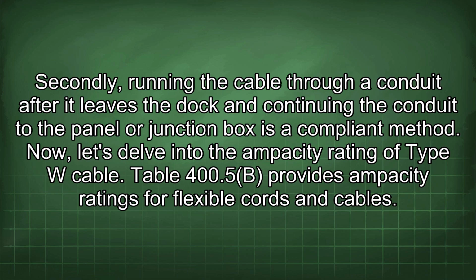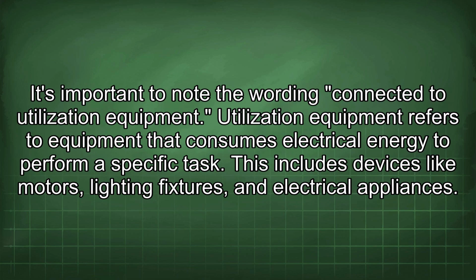Now let's delve into the ampacity rating of Type W cable. Table 400.5b provides ampacity ratings for flexible cords and cables. It's important to note the wording connected to utilization equipment. Utilization equipment refers to equipment that consumes electrical energy to perform a specific task. This includes devices like motors, lighting fixtures, and electrical appliances.